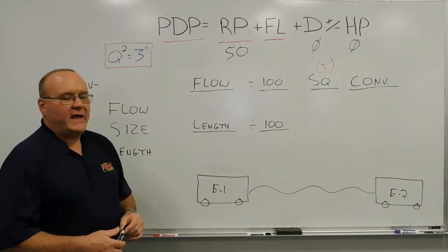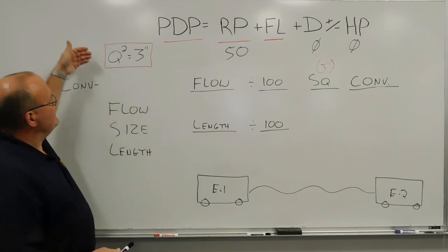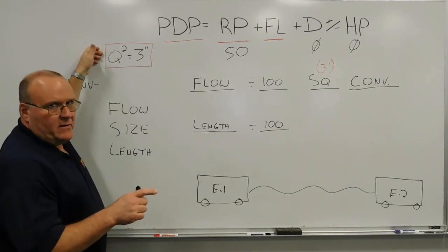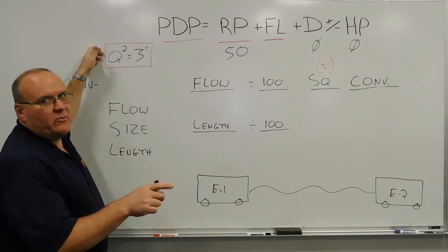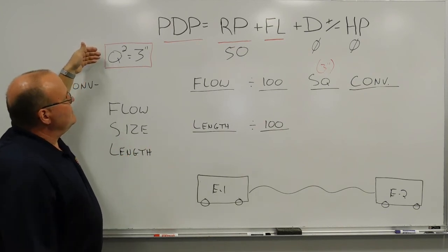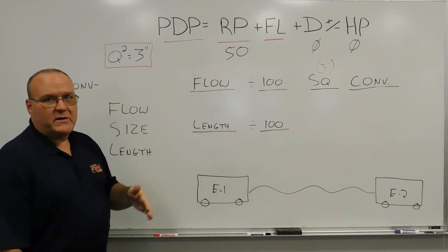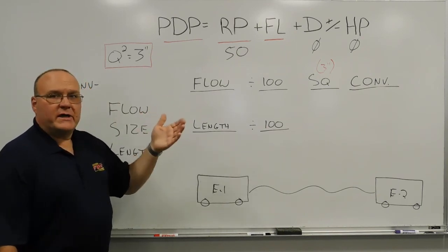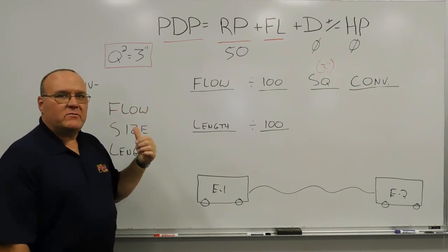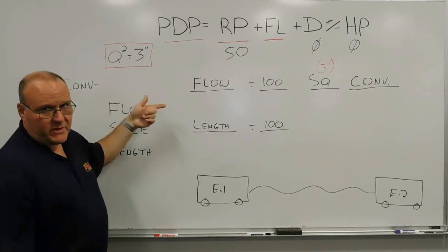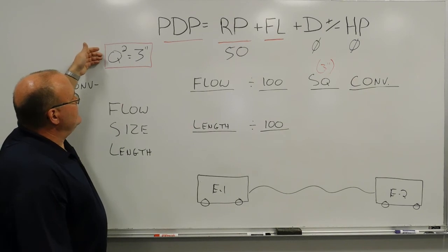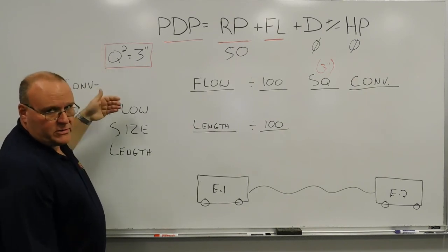And we're working with the Hand method, the Q-squared method, and then we're using conversion factors. The Q-squared baseline always gives us a 3-inch hose number. That's the 3-inch friction loss in a 100-foot section of hose. And then to go from 3-inch hose to another hose size, you convert by either multiplying or dividing. If you go from 3-inch hose to 2.5, which we did in our previous training minute, we had the conversion factor of times 2. So Q squared times 2 for 2.5-inch hose. We also did conversion from 3-inch hose to 4-inch hose.